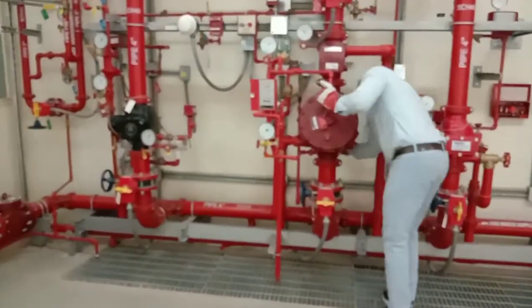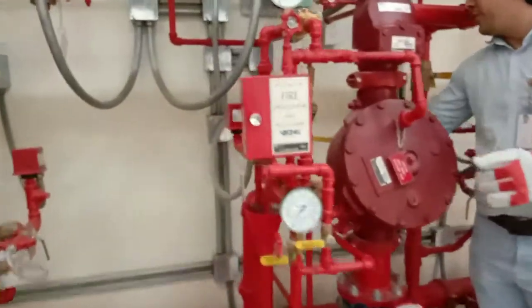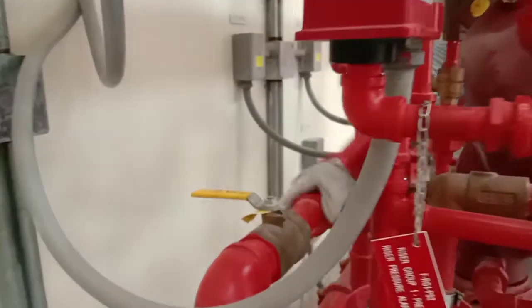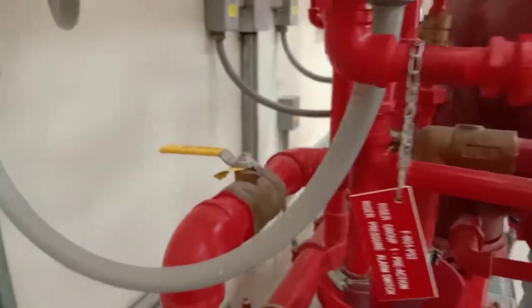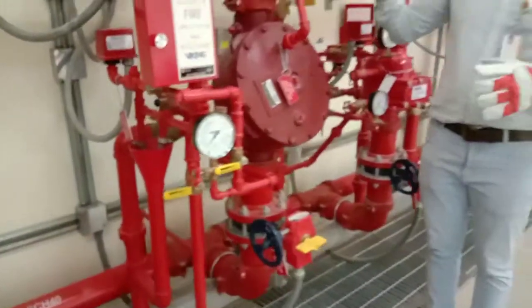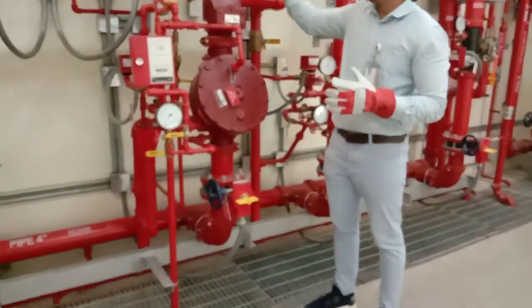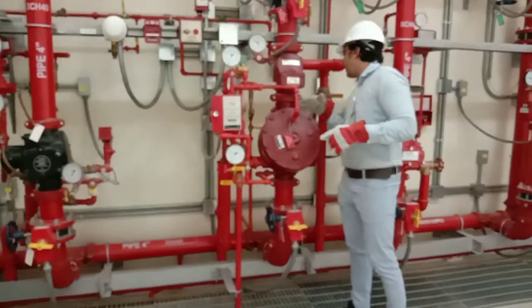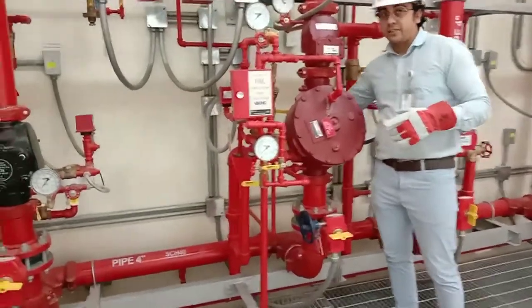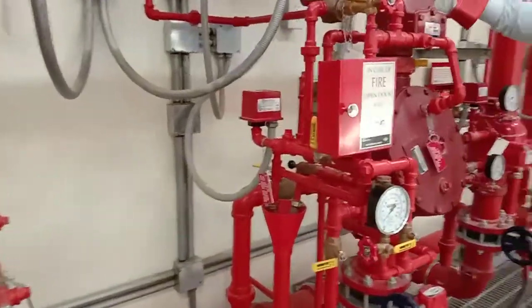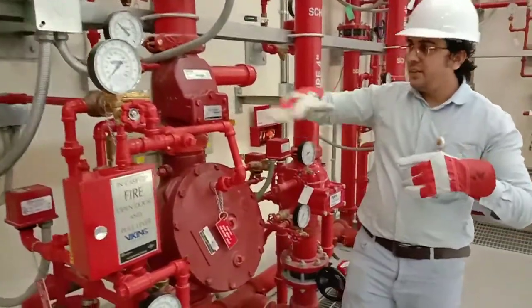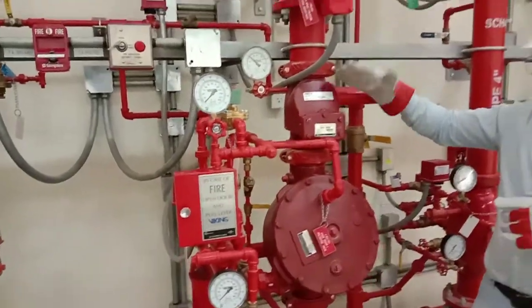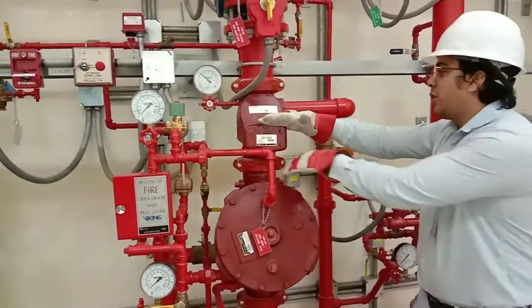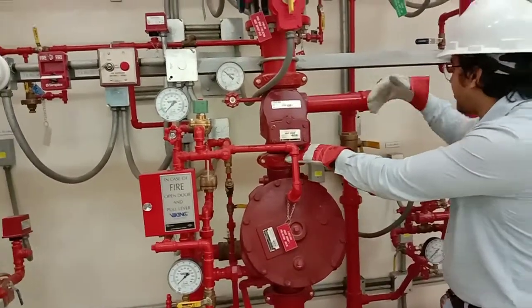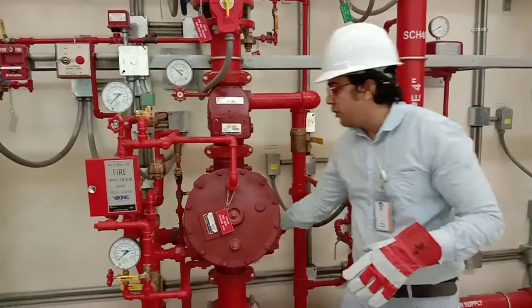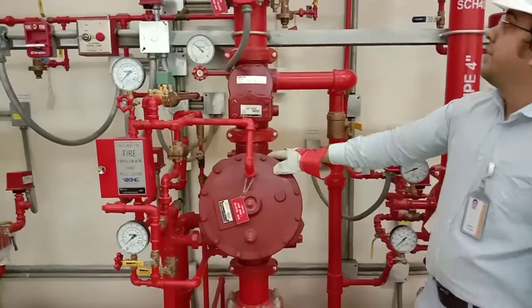And we have a drain connection at this location. If we have to drain, we can drain from this location, right? If the system got discharged, we have to drain the water completely because it's a dry system. In a dry system, if there is water trapped inside the pre-action system, it will corrode the piping very easily. So this is the low level drain. It will drain from here, and here we have another drain, because as I said, there is a check valve. Once the flow is stopped, the clapper will hold, so the water will not come below that one, right? So we have to discharge from this side. This is the high level drain valve. This is the low level drain valve. We need to discharge this system completely.